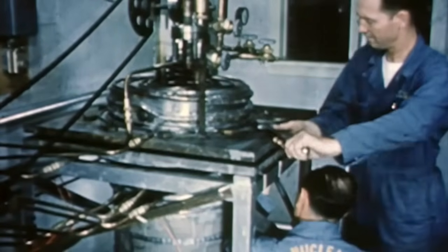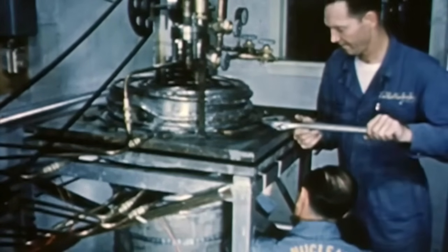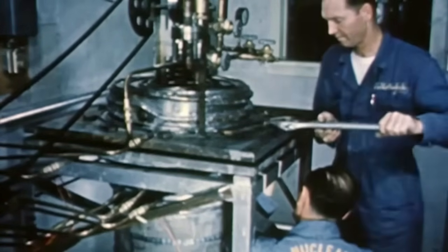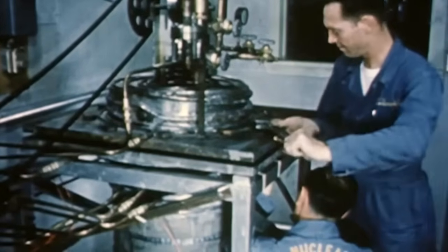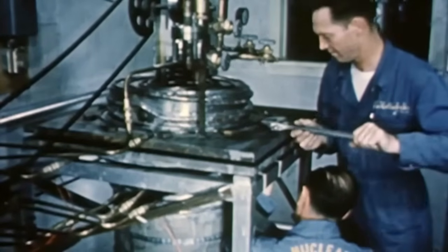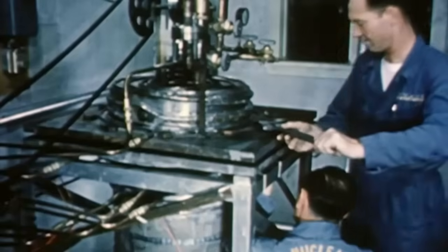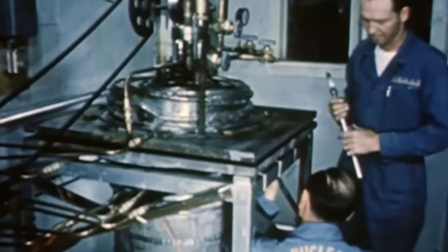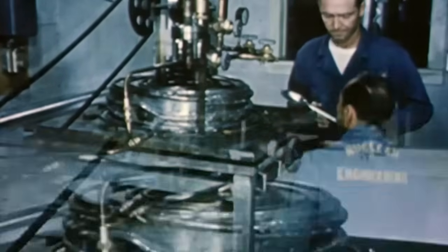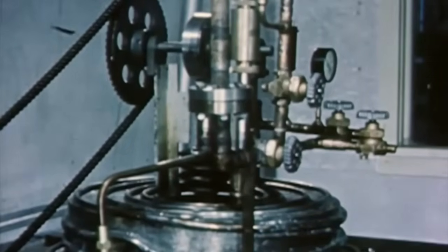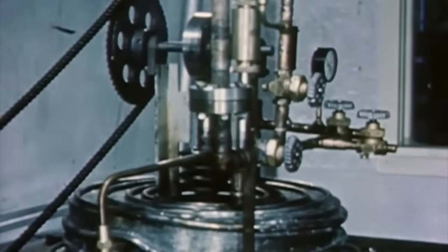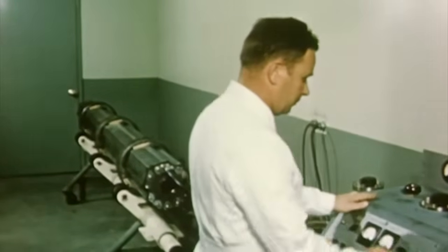The can was immersed in sodium and evacuated. Sodium temperature was maintained at 950 degrees Fahrenheit. Any break in the welds would be detected by a sodium leak indicator. Early failures were observed, which led to an improvement in head design. Later heads have survived cycling tests equivalent to nearly 8 years of operation in the sodium reactor experiment.